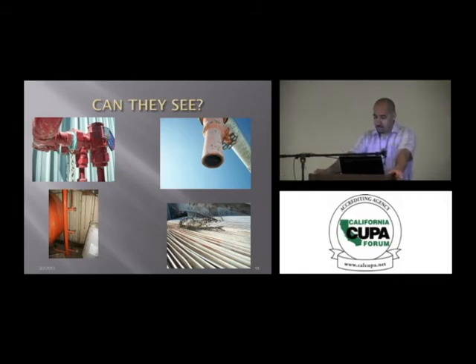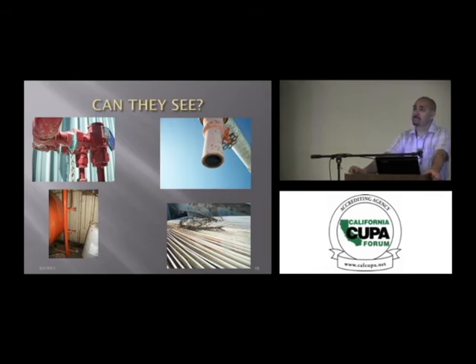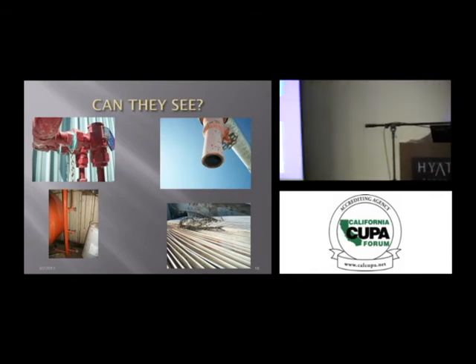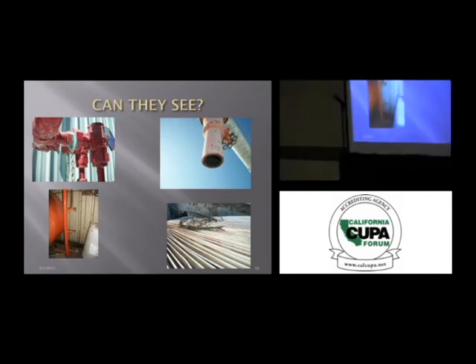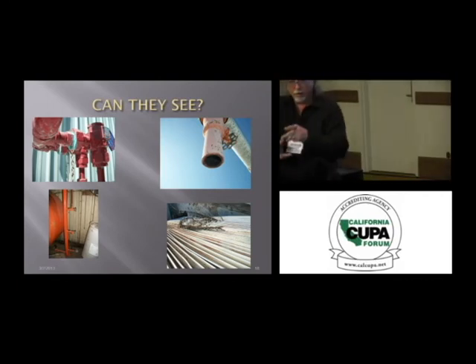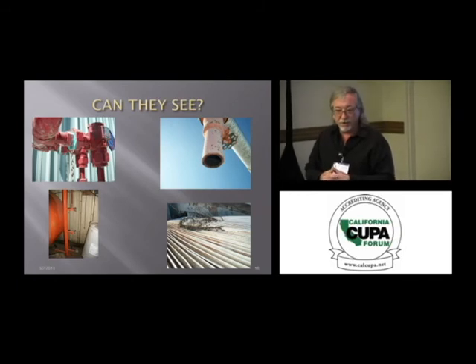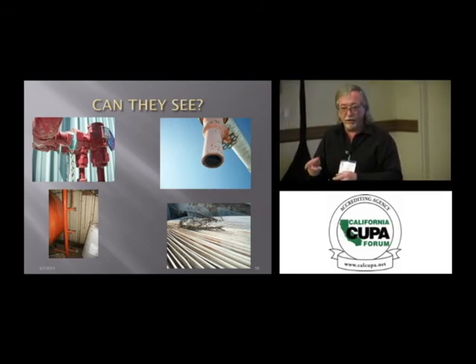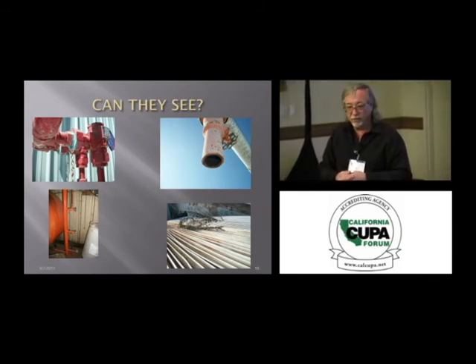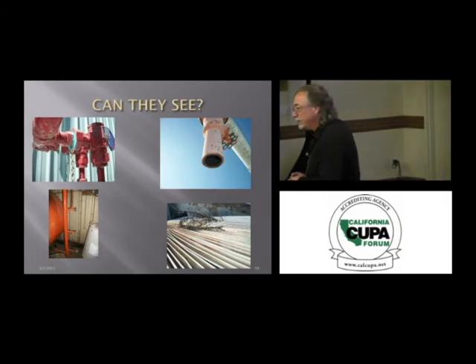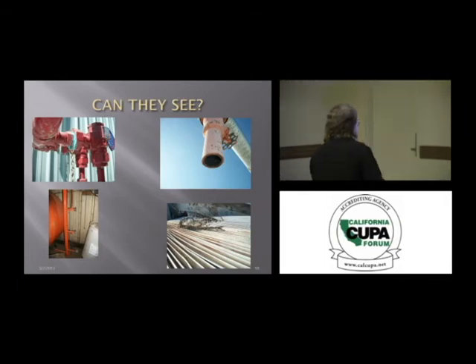There's three possibilities for that. What was that? It's got a gold seat, brass, copper. Galvanized fittings, yes. Yep, galvanized fitting with the wrong type of seat. Yep, very good. Okay, and what else? Ammonia has seen that, huh? Is that ammonia on the inlet or the outlet where that green is? It's on the outlet, which means ammonia has passed through that, or, as Don said, there's moisture.